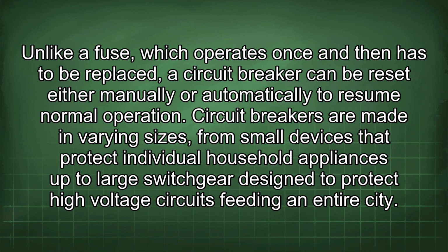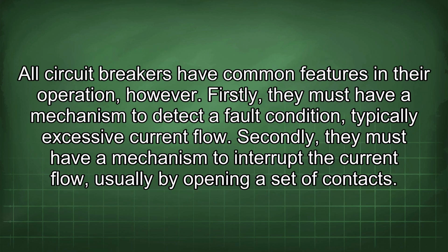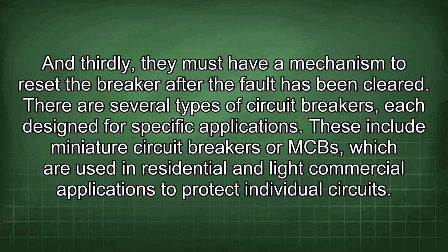Circuit breakers are made in varying sizes, from small devices that protect individual household appliances up to large switchgear designed to protect high-voltage circuits feeding an entire city. All circuit breakers have common features in their operation, however. Firstly, they must have a mechanism to detect a fault condition, typically excessive current flow. Secondly, they must have a mechanism to interrupt the current flow, usually by opening a set of contacts. And thirdly, they must have a mechanism to reset the breaker after the fault has been cleared.